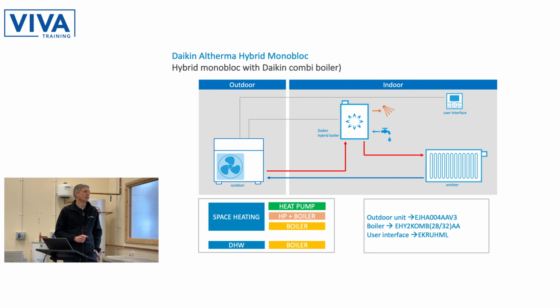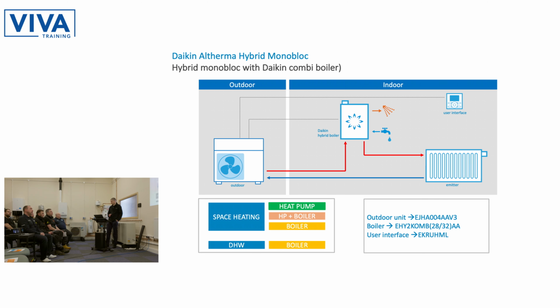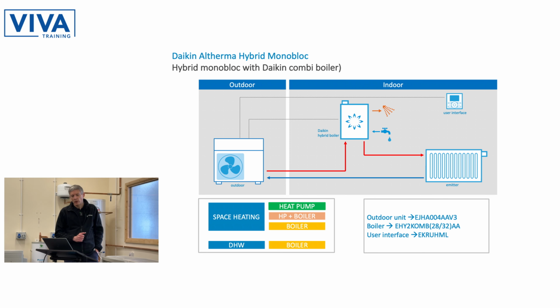Now for domestic hot water, it's the boiler only, so it's a combi boiler as in its standard setup, and so that will do all of the hot water by itself. The advantage of that is that the heat pump can continue to operate in space heating while you've gone away to the boiler to do some hot water.